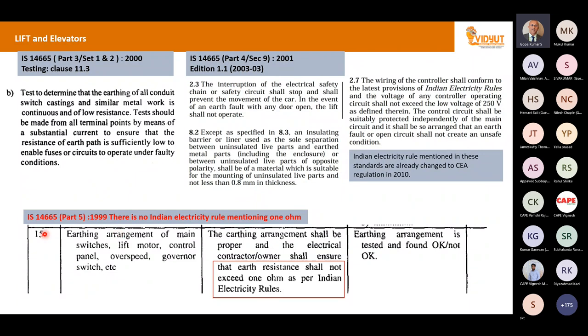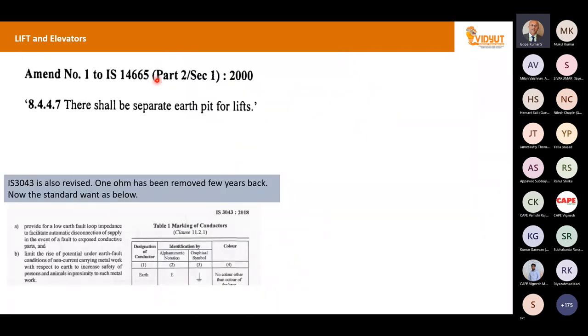In clause 15, the earthing arrangement shall be proper, and the electrical contractor shall ensure the earth resistance does not exceed 1 ohm as per Indian Electricity Rules. Actually this is a mistake in the standard. Also, one amendment to the lift standard, clause 8.4.4.7, states there shall be a separate earth pit for the lift. All these mistakes happened over a period of time.